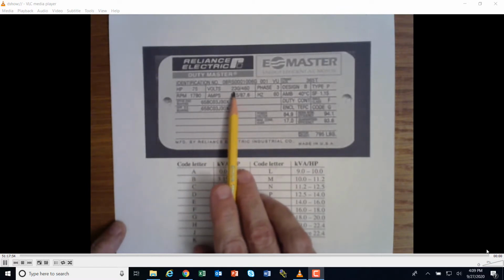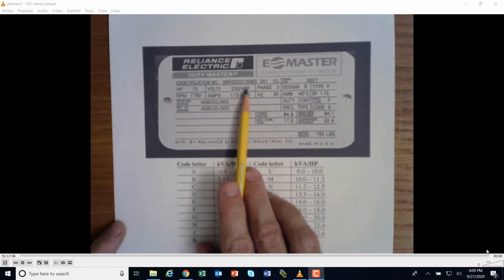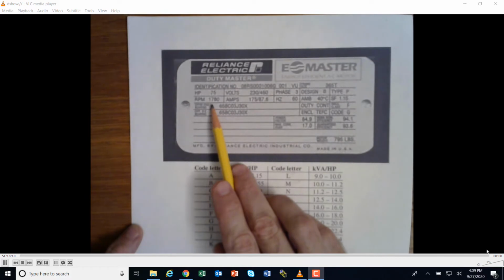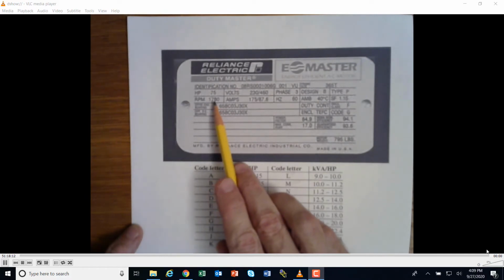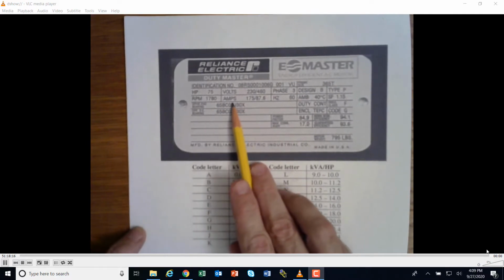It's running at 230 and 460 volts, okay? So that's the first thing that we need to know: voltage is 230 or 460. I think we're going to take a look at this running at 230 volts, okay? The RPM is 1780. Okay, so it's running just a little bit off synchronous speed of 1800.